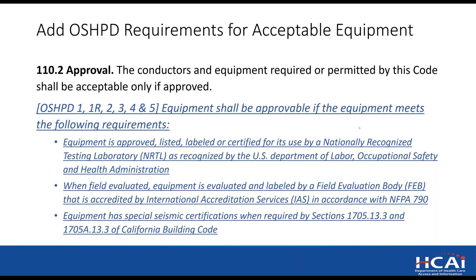Next, we're talking about the requirements for approval, and we've revised this. Generally, this first bullet, equipment is approved, listed, labeled, is in our note. We've added a bullet: when field evaluated, equipment is evaluated and labeled by the field evaluation body that is accredited by the International Accreditation Service, IAS, in accordance with NFPA 790. And then the third one is just a reminder that the equipment has to have special seismic certification as defined in the building code. Next slide, please.